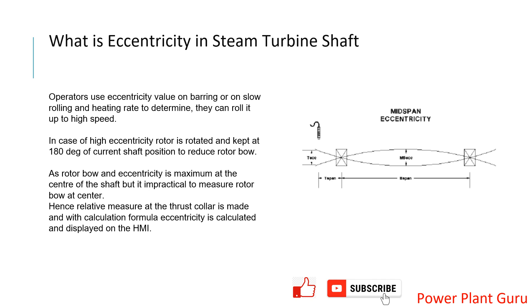Operators and turbine users use the eccentricity value when the machine is on a slow rolling speed and you are heating the machine, to make sure that the rotor doesn't have a bow condition when you are starting. The eccentricity value depends on the type of machine and its megawatt rating — based on rotor length and other factors — and may vary for machines from 35-40 megawatt up to 600 megawatt. Consider a condition where your machine is coming from a large outage and you see the eccentricity value is too high — higher than you have seen before.